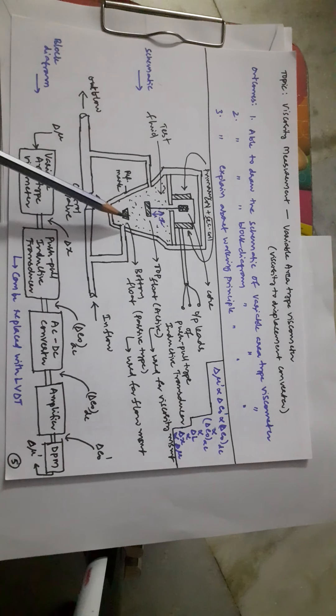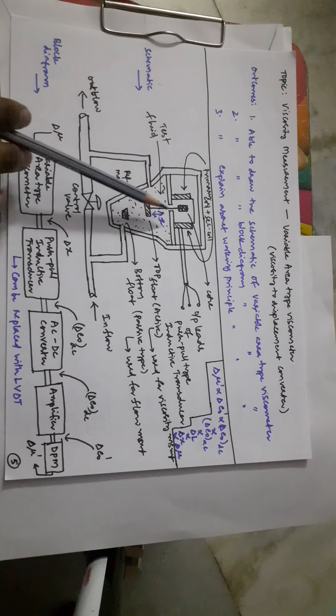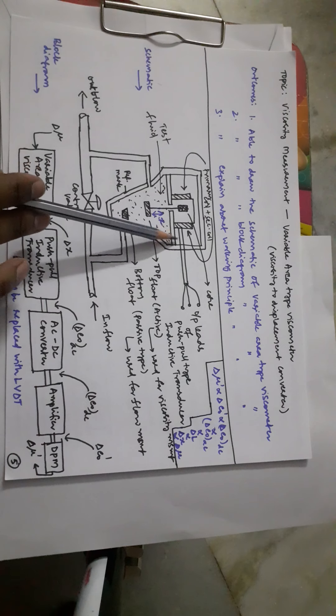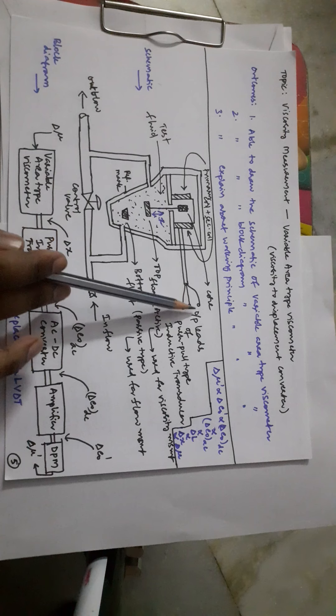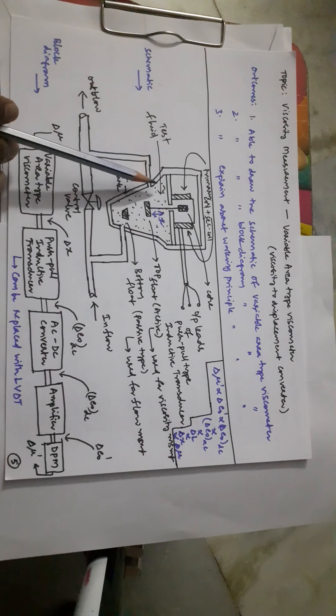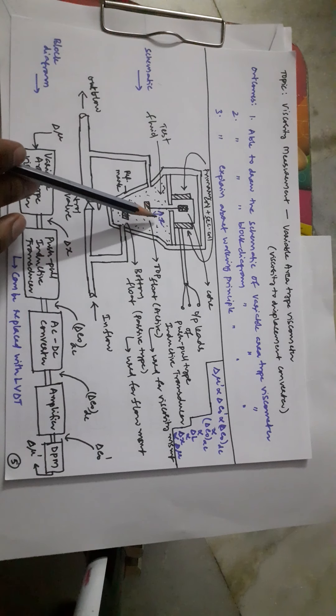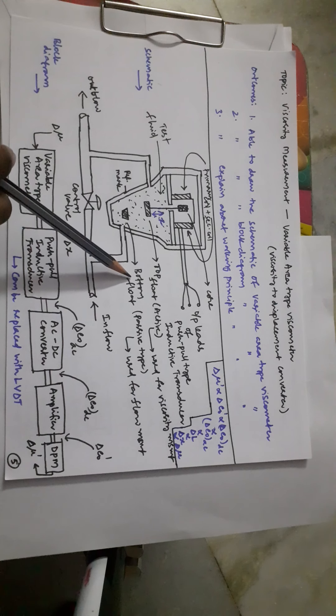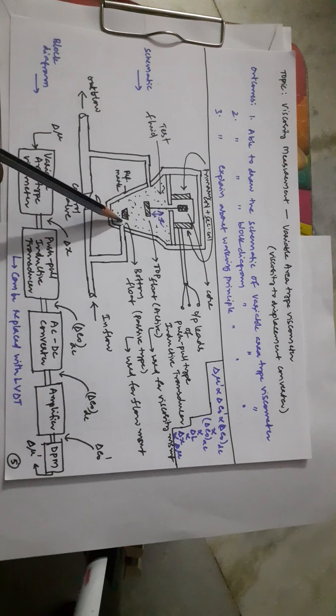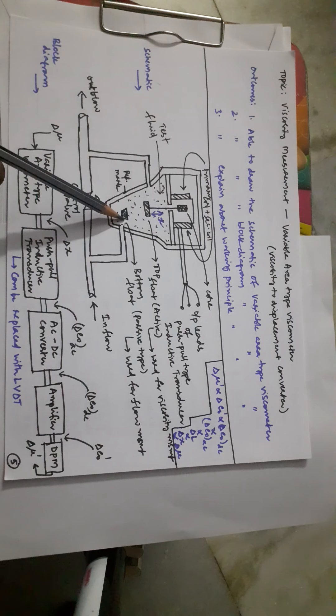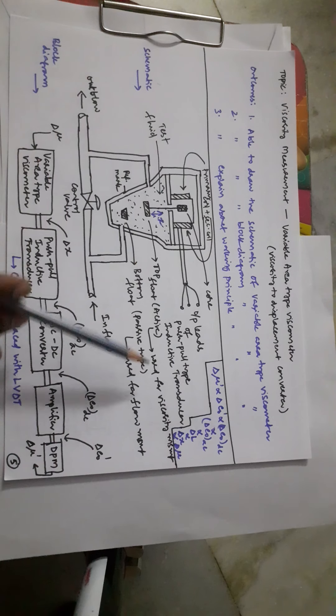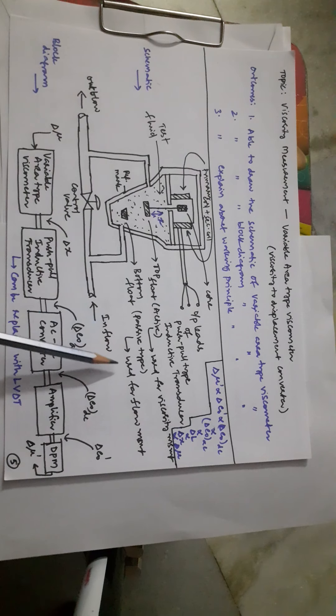The flow enters an area where two floats are present: a bottom float and a top float. The top float is connected to a push-pull type inductive transducer coil setup, from which electrical output leads are taken. The displacement of the float is referred to as X. The bottom float is a passive type used for flow rate measurement, while the top float is the active type used for viscosity measurement.